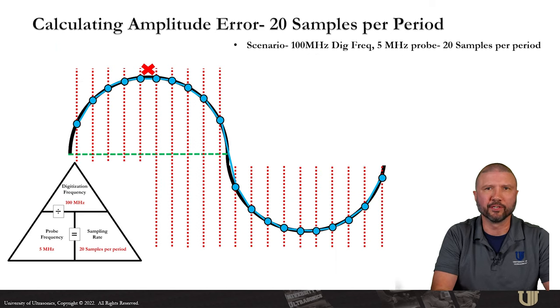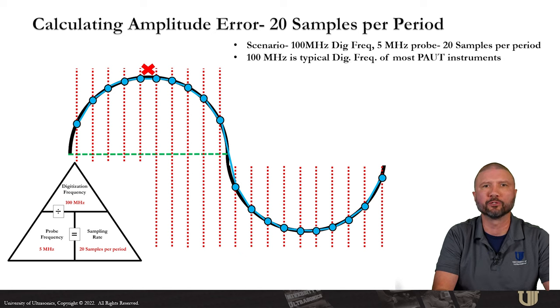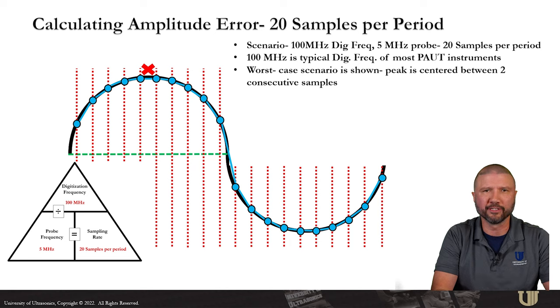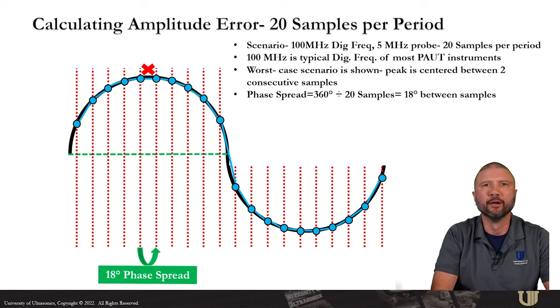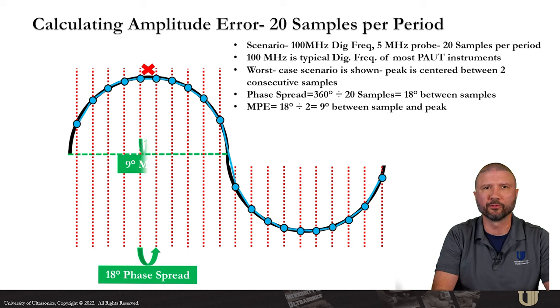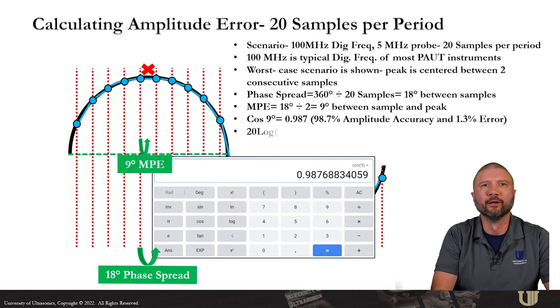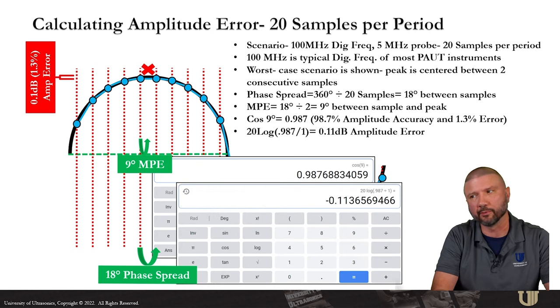For the next scenario, we'll consider using a 5 MHz probe and a 100 MHz digitizing frequency, which would result in 20 samples per period. 100 MHz is the default digitization frequency in many of today's instruments, and that's before any compression or subsampling or points quantity. More on that later. The more samples you collect, the closer and closer you get to the peak position, no matter where the samples are along your waveform. Which means the better our timing and amplitude fidelity will be. The worst case scenario is shown again, where the peak is centered between two samples. But notice, there's not a lot of daylight between the samples and the peak. Phase spread is going to be about 18 degrees between samples. And if I divide that by two, I can show that there are 9 degrees between the sample and the peak. Cosine of 9 degrees is about 0.987, which would be 98.7 percent accuracy and about 1.3 percent error. And if we convert that to a dB, we're about 0.1 dBs away from the peak.